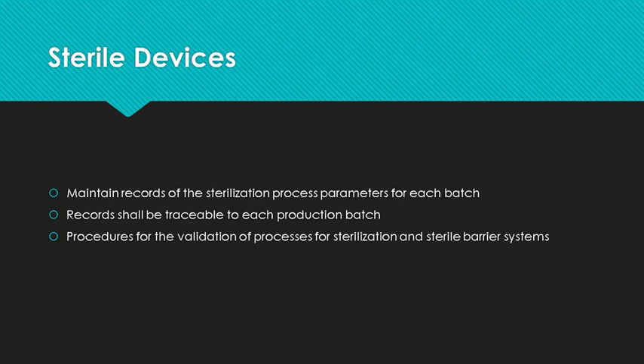Now let's talk about a special category: sterile devices. Procedures for validation of sterile processes must be determined and performed. Organizations producing sterile devices must maintain records of sterilization process parameters traceable to each batch and verify they are in compliance with the validated parameters.